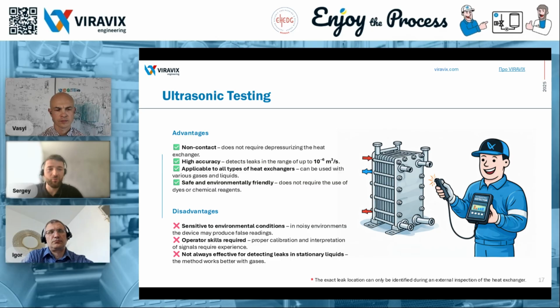The advantages of this method include that it is non-contact, meaning it does not require depressurizing the heat exchanger. It also offers high accuracy, detecting leaks in the range of 10 to the power of -6. Another advantage is that it can be applied to all types of heat exchangers, meaning testing can be performed with various gases and liquids. It is also safe and environmentally friendly, as it does not require the use of dyes or any chemical reagents. However, there are also some disadvantages.